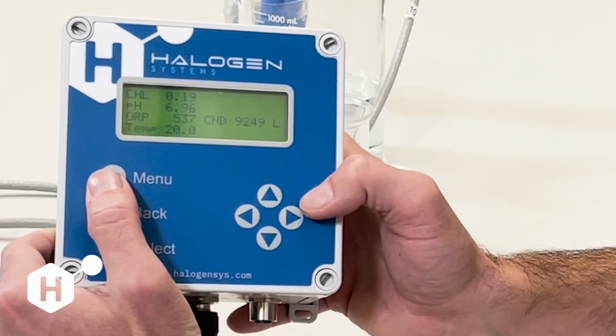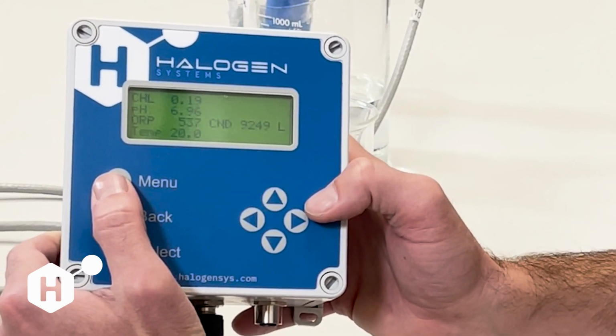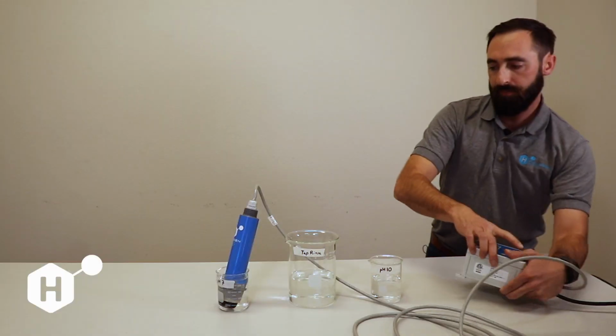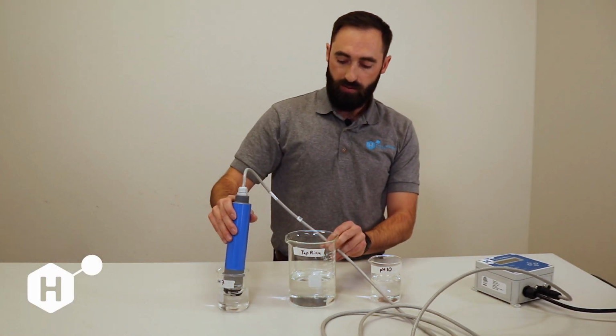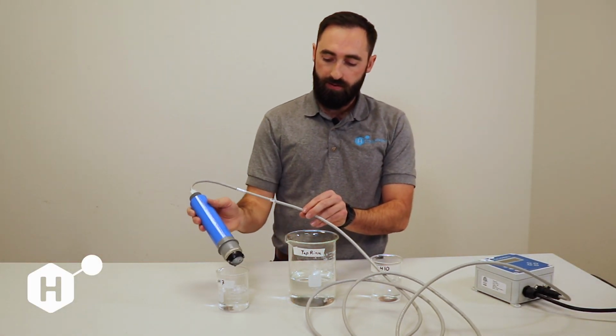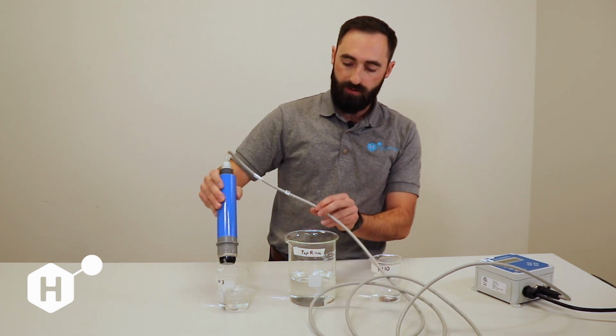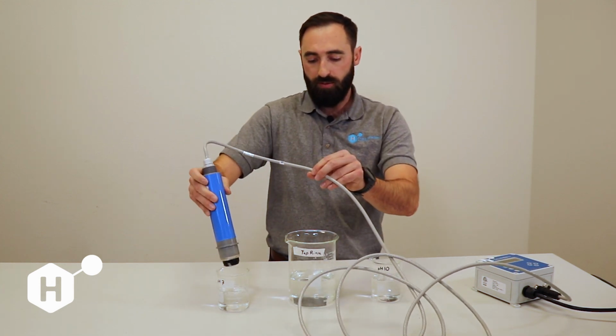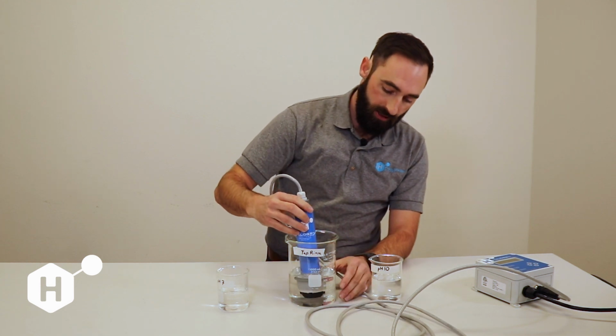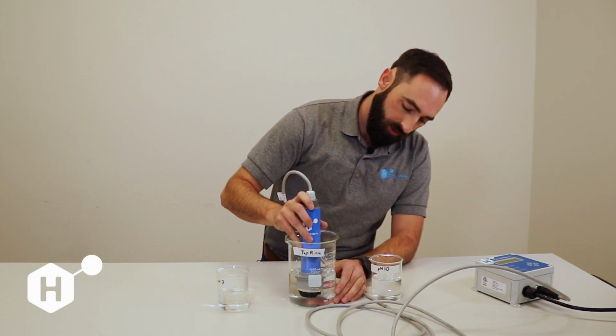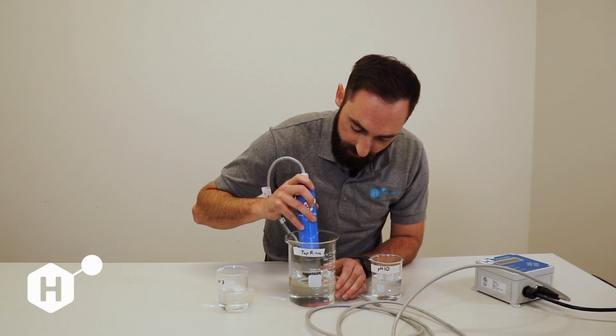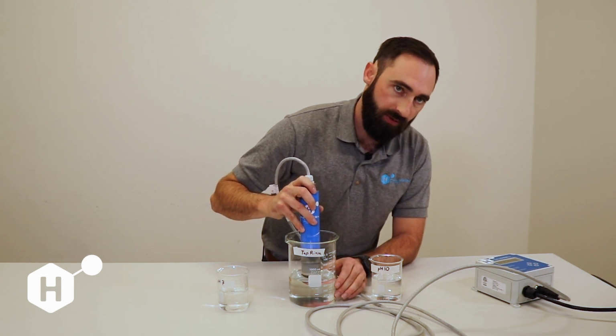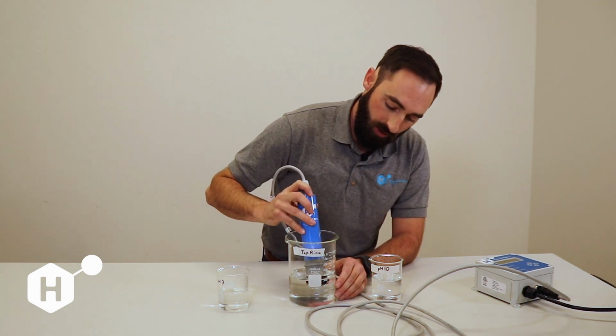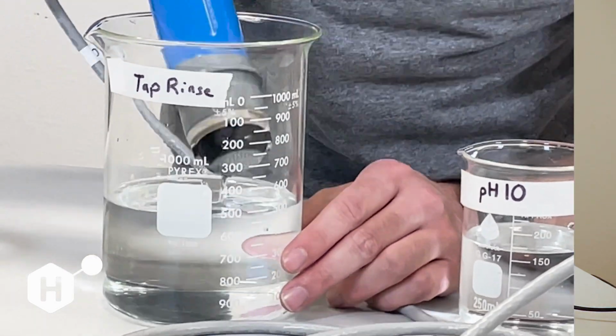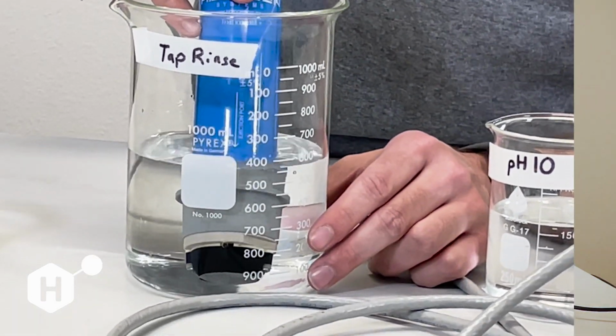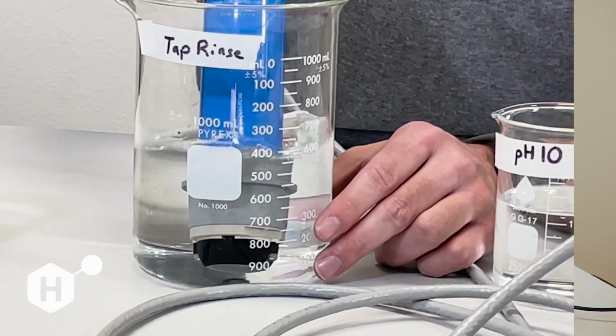So now that I know that the 7 pH calibration was good, I'm going to go ahead and rinse the sensor. We're going to pull it up out of the 7 buffer, get as much of that 7 buffer out of there as you can, moving the sensor around. And then we're going to put it into our rinse solution. Now we're going to want to do the same thing here. See how we're not getting any water flow across the sensor surface? We're going to want to tilt the sensor so that the ejection port is facing up a little bit and give it a little bit of a swirl.